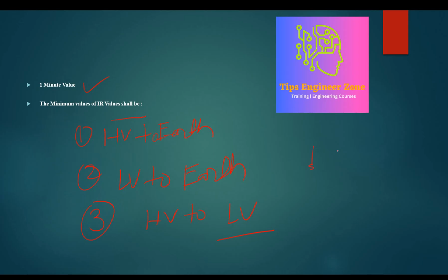In case of 3-phase, this is a 3-phase transformer. Short all the windings, and you can measure between HV to LV. So in this way you can measure the insulation resistance value easily.